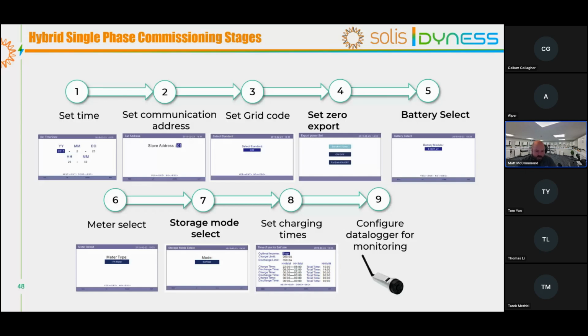I didn't really discuss the discharge window. What I will say about that is that it's not common in the UK to use a discharge window, so you would kind of ignore that. Ultimately, if you set a discharge window, if you said between the hours of 12 and 2, I wanted to discharge 50 amps, then it would just take the energy from your battery, ignore what's happening in the meter, and then discharge 50 amps. So what you would see is you would see the load get covered, then the rest would just be exported to the grid.